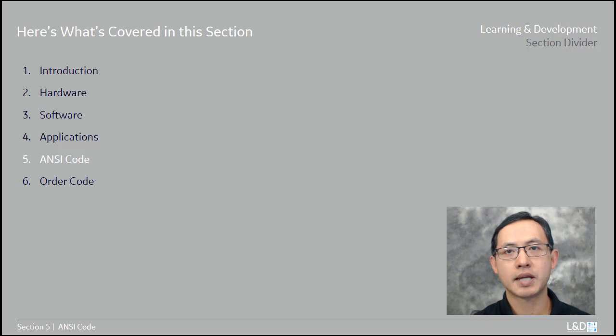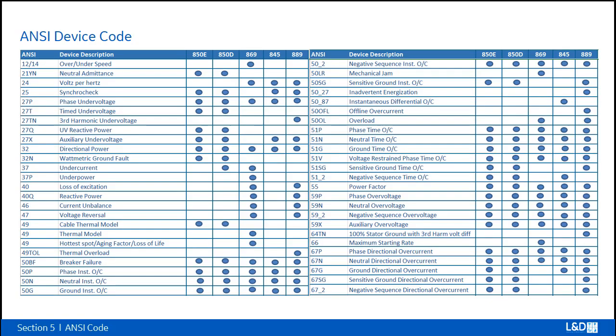In the ANSI code session, we are going to introduce the common platform elements across all 8-series relays. Then we'll introduce the specific protection elements for each special application: the feeder, motor, transformer, and generator. In the ANSI device code comparison table, we can see the elements for all the 8-series platform, and we can also see some elements are only specific to a certain type of relay.